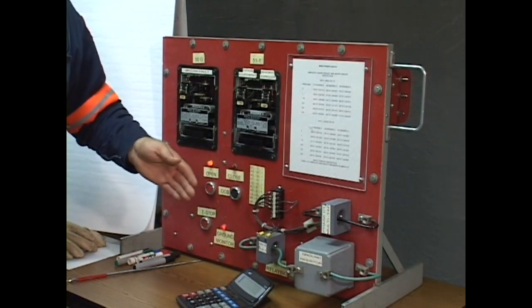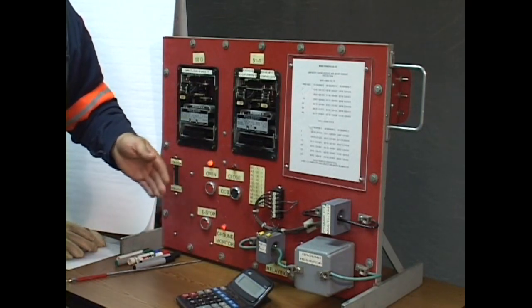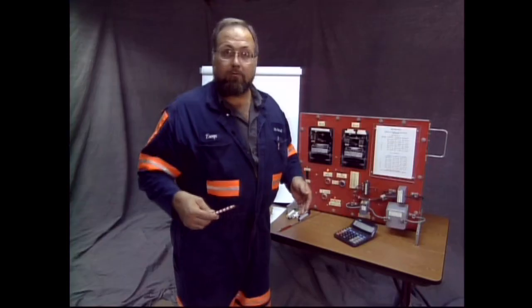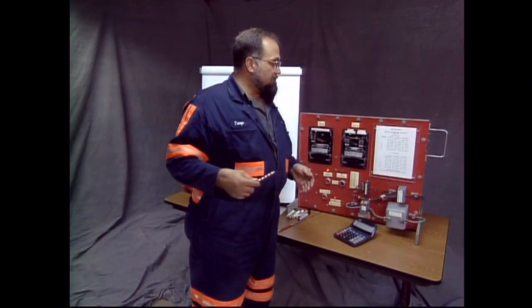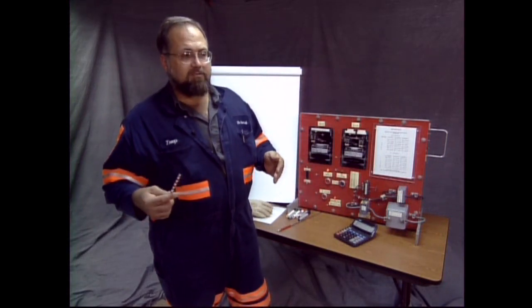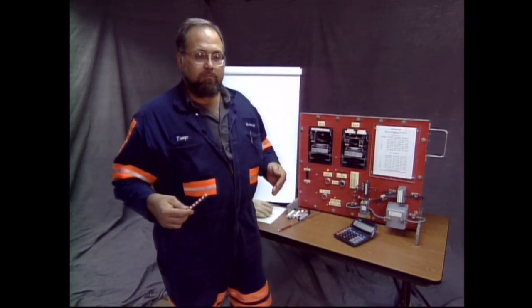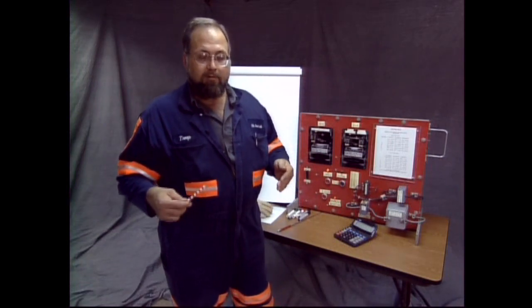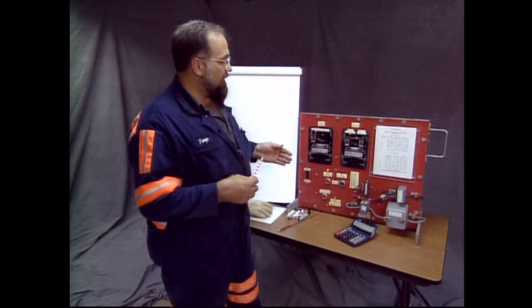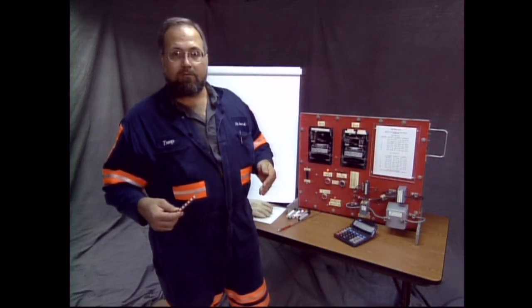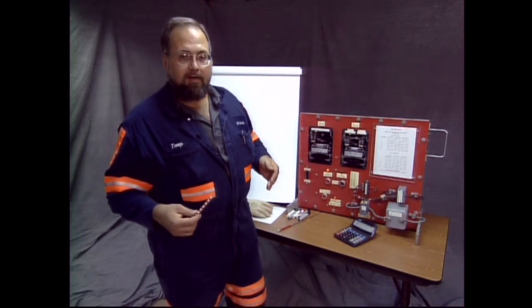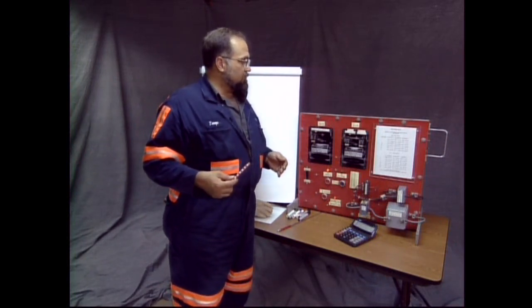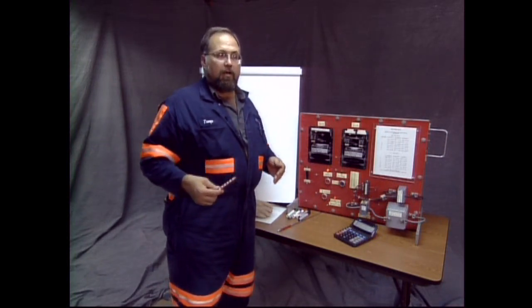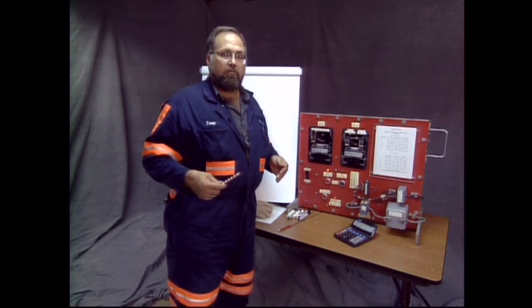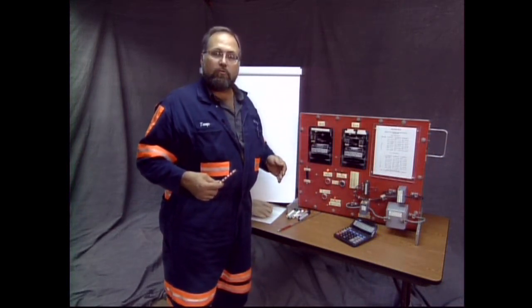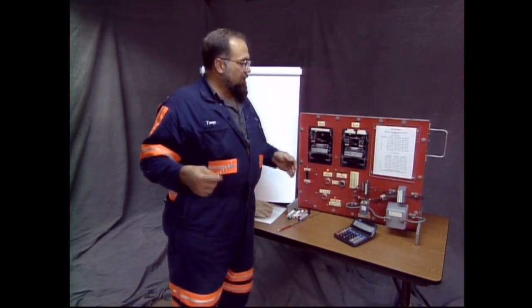That phase doesn't appear to be connected to the CT. Your answer to that, it's magnetically coupled. Okay? Those type questions, when you're asked these questions, this allows you to show that you really have a grasp of the panel, of the protections, of the concept of high voltage relaying, high voltage monitoring. And these are not designed to trip you up. They don't want to try to fail you, but they want to know that you indeed understand what you're being certified for. So just be calm and be relaxed.